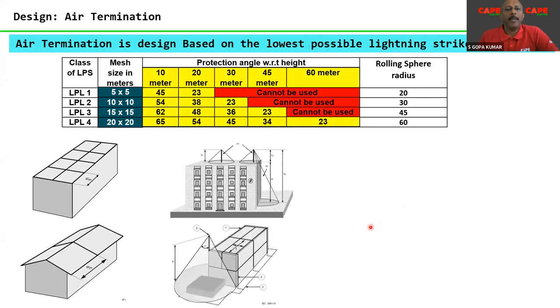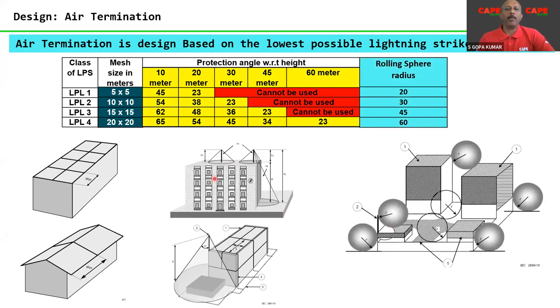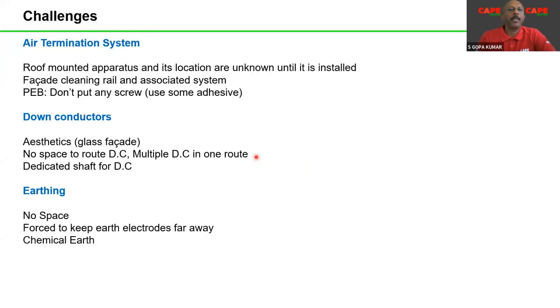Now, designing of air termination, let me skip it. There are several techniques for designing the air termination, called the mesh method, the protective angle method, and the rolling sphere method, not very important for this presentation. Let me skip it. Challenges. The challenge which we face in every installation is that most of the time when we get the drawing, the construction is already over. The structure is already over. And then they ask us to make a design. And once we tell them, sir, there is an important subject called separation distance. You have to keep your air terminal 1 meter away from the building or 2 meters away from the building.